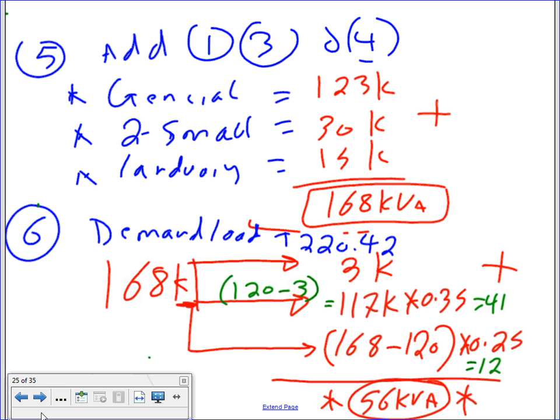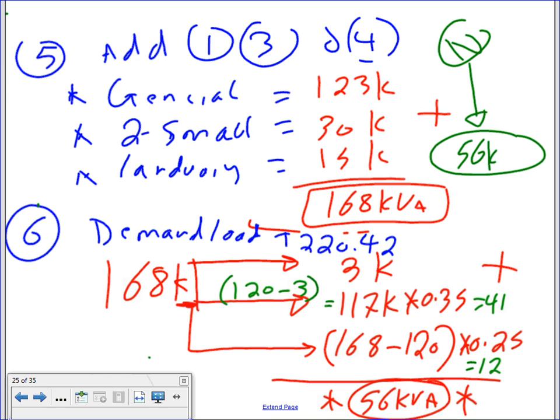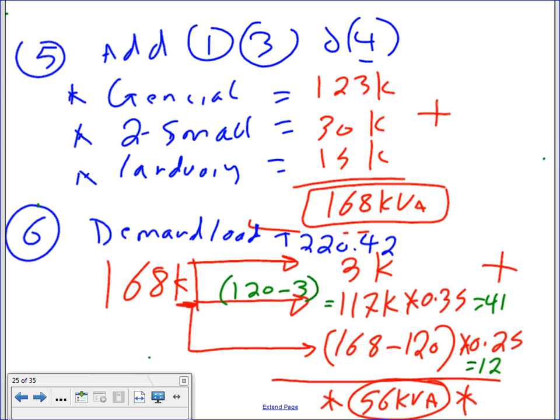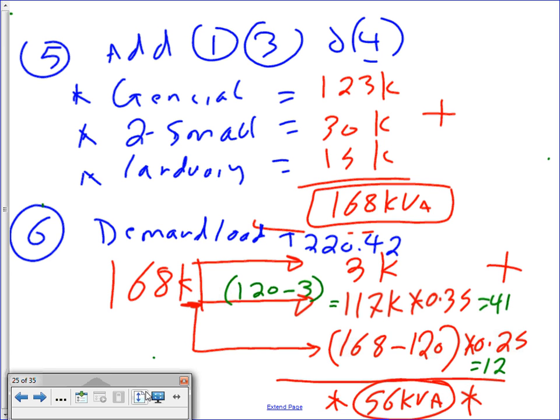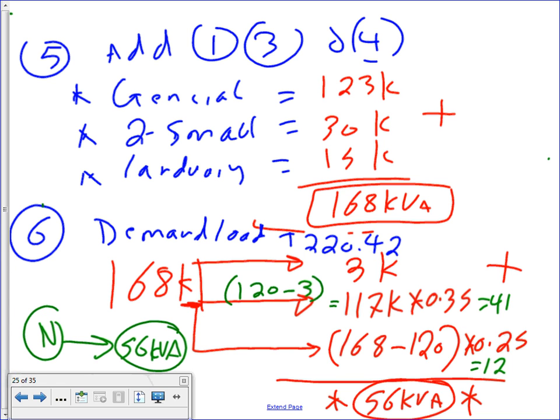So for this step, all you have to do is put neutral here and count everything that we did. The same number, 56 kVA, will count towards the neutral. All of them will count towards the neutral. Maybe we should put them under step 6, because that's how they should be here. So here's my neutral, and the size of my neutral would be 56 kVA. Okay, any questions, guys, about this? Straightforward. All of them will count the same, no changes.